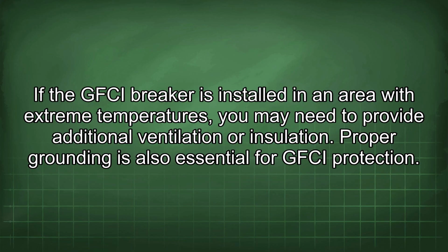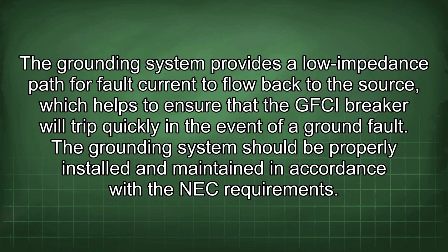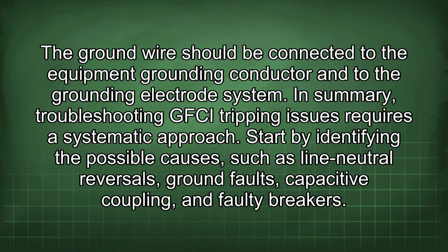Proper grounding is also essential for GFCI protection. The grounding system provides a low impedance path for fault current to flow back to the source, which helps to ensure that the GFCI breaker will trip quickly in the event of a ground fault. The grounding system should be properly installed and maintained in accordance with the NEC requirements. The ground wire should be connected to the equipment grounding conductor and to the grounding electrode system.